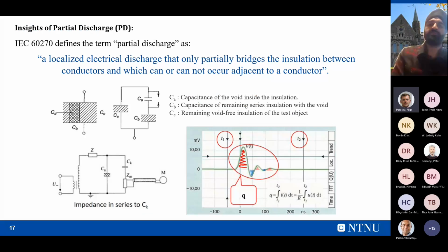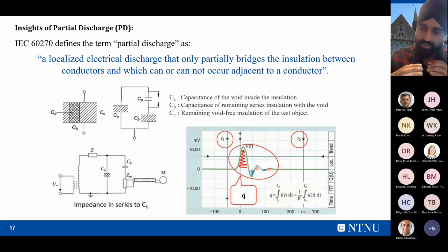So coming back to the partial discharge slide. Now this coupling capacitor is connected with Zm, a series impedance to protect the system. This is also a series impedance, to protect the high voltage source, because there should not be any interference between the input signal and the current signal coming from the discharges. Now what we are doing is charging this capacitor at a particular voltage, or at the rated voltage. If there is any void inside the insulation and that void gets discharged, then once it is discharged it will start charging again, and the charging of that void will take place from this capacitor.